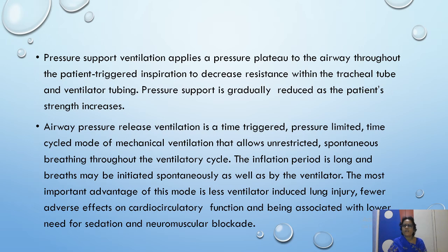Next is pressure support ventilation. It applies a pressure plateau to the airway throughout the patient-triggered inspiration to decrease resistance within the tracheal tube and ventilator tubing. Pressure support is gradually reduced as the patient's strength increases. Pressure support ventilation gives support only when the patient is not able to take respirations. When the patient is able to, it allows the patient to take breaths spontaneously, thereby strengthening the patient's respiratory muscles. And another one is airway pressure release ventilation.